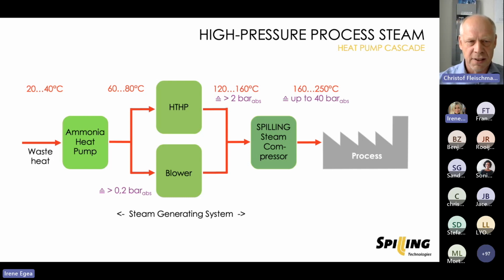And some of these new high temperature heat pump systems have in their program also a steam producing part on the sink side, so that they can supply with these machines or with these systems low pressure steam with, say, 2 to 5 bar.